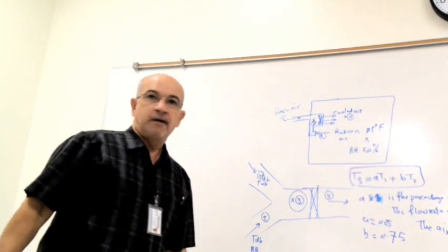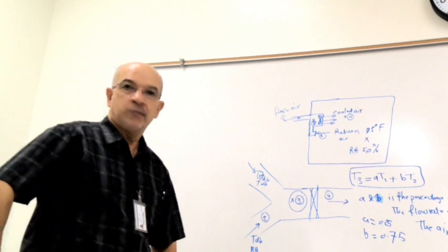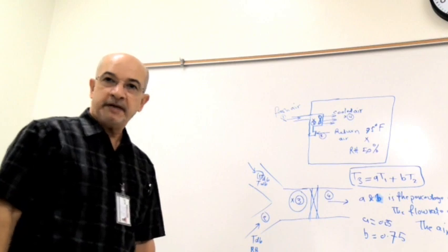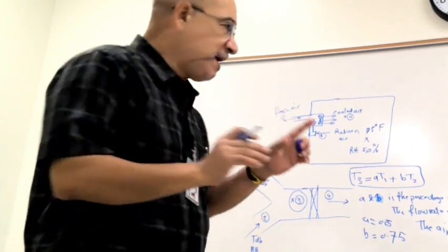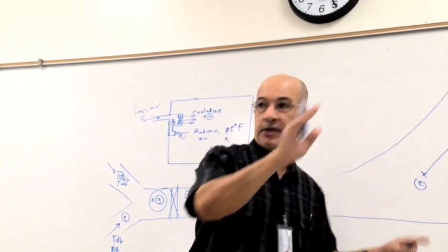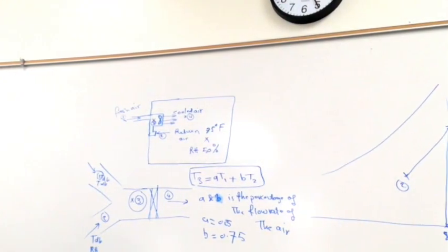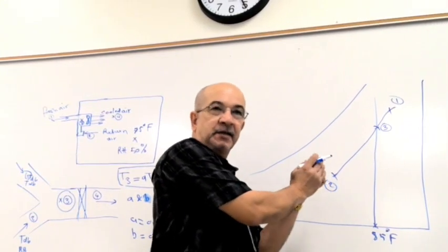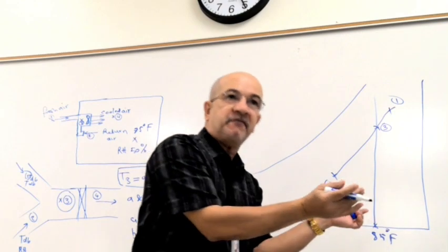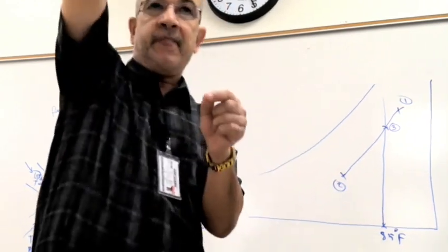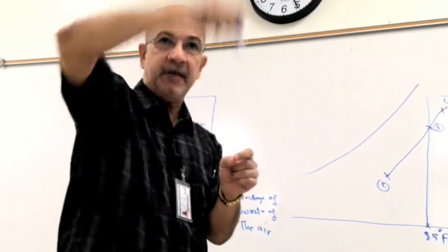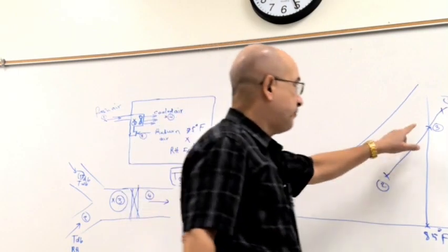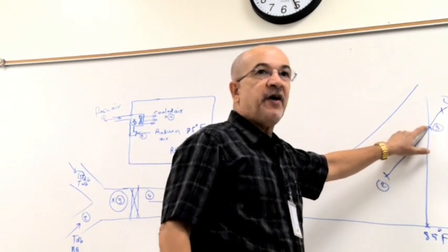So when you come to the third temperature, which is 85, you just draw a line all the way up, and where it intersects the process line, that's point 3. You have vertical lines on the psychrometric chart, which are constant dry bulb temperature. Put your ruler parallel, or you'll find the constant dry bulb line for 85 already drawn on the chart. Just follow it, and where it intersects this line, we find point 3.